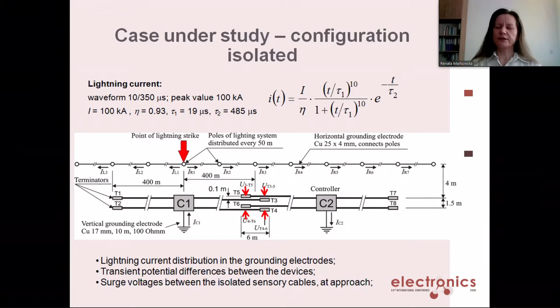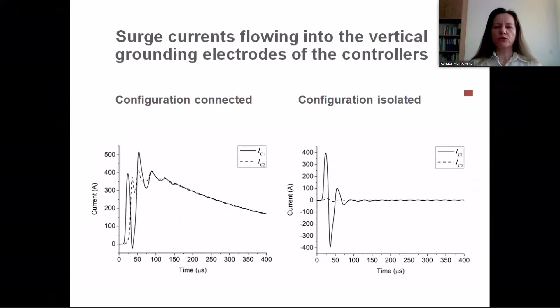The surge currents flowing into the vertical grounding electrodes of the controllers differ visibly for both configurations. In the case of the isolated configuration, only the short time component of oscillatory type is present, whereas for the connected configuration, there is also the long duration component, which resembles the waveform of the lightning current. The surge currents in the outer conductors of the sensory cables are very similar to the currents flowing into the vertical grounding electrodes, but they have much higher oscillatory type components.